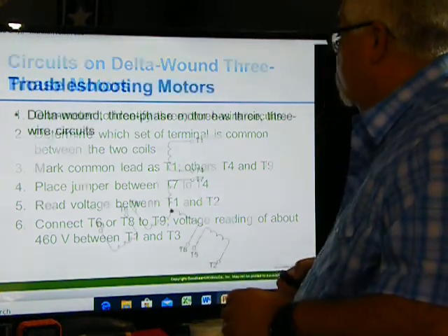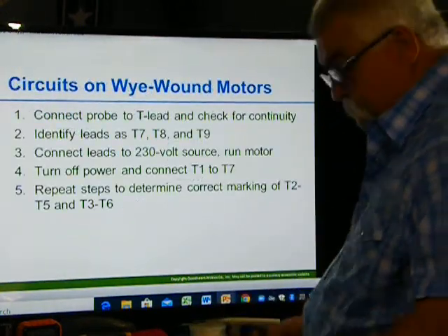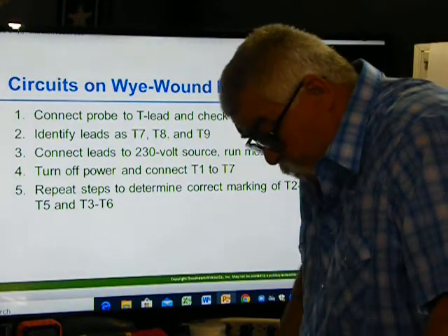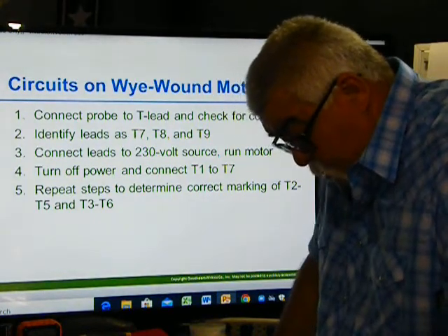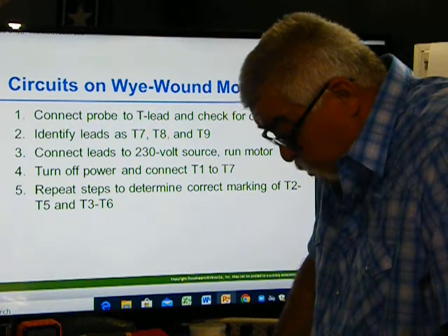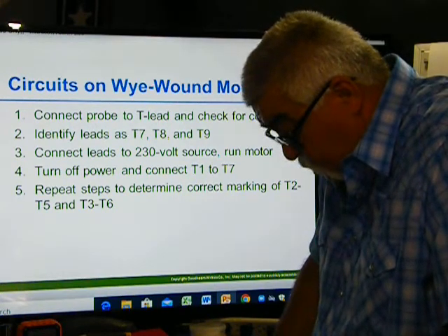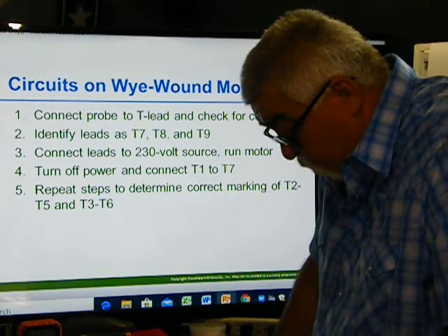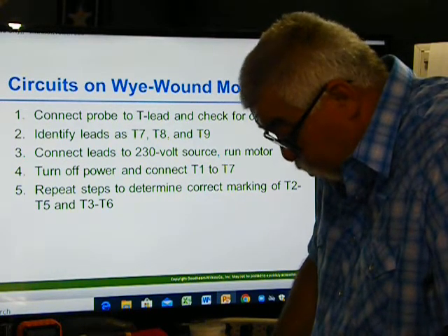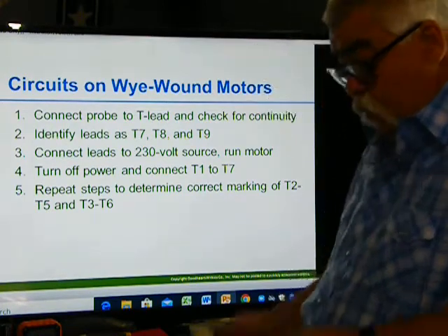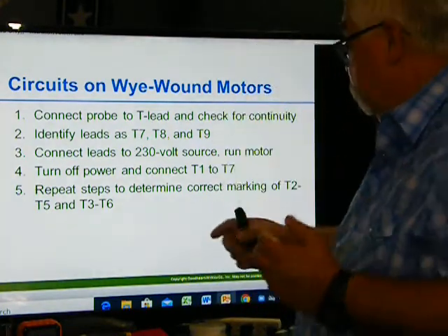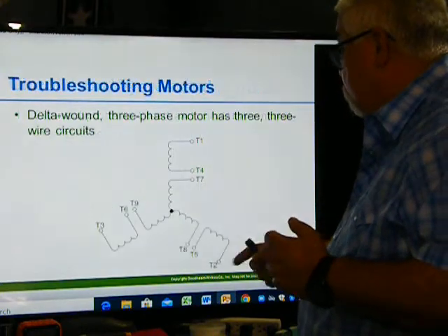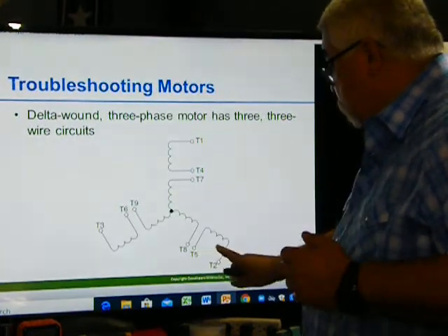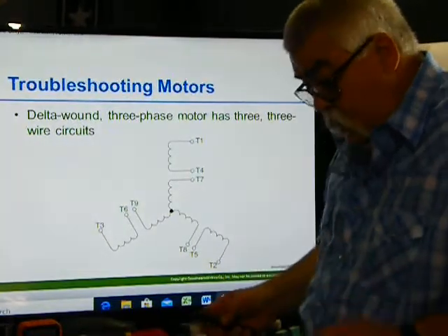It says, let me go back here real quick. It says connect lead, identify the lead to a 3-wire circuit, the T7, T8, T9 in any order, and temporarily mark the leads in the 2-wire circuit T1, T4, T2, T5, T3, T6. So once you get your pairs, once you get these 3, then you can temporarily identify them.